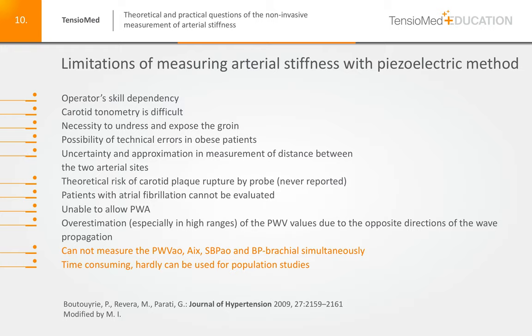Measuring arterial stiffness with the piezoelectric method carries several limitations: the operator needs skill, carotid tonometry is rather difficult, the patient must be undressed, there is possibility of technical errors in obese subjects, uncertainty and approximation in measuring the distance between the two arterial sites, a theoretical risk of carotid plaque rupture by the probe, and patients with atrial fibrillation cannot be evaluated. At that time, this device was unable to measure pulse wave analysis — namely the augmentation index and central blood pressure. This method also overestimated aortic pulse wave velocity, especially in high ranges, because of the opposite direction of wave propagation.